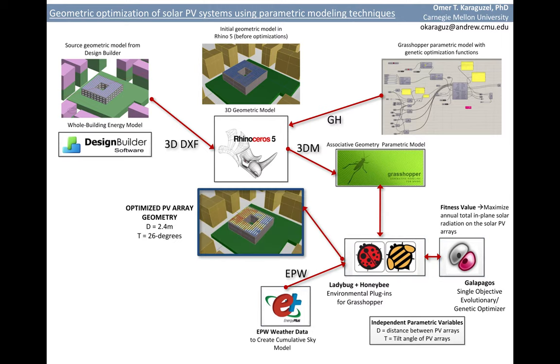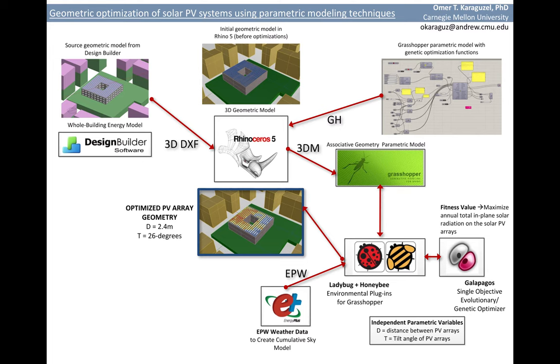After a certain number of iterations, the optimizer evaluates all candidate solutions and finds the optimum PV geometry. In our case, we ended up with 26 degrees tilt angle, the vertical angle, and 2.4 meters of array distance.